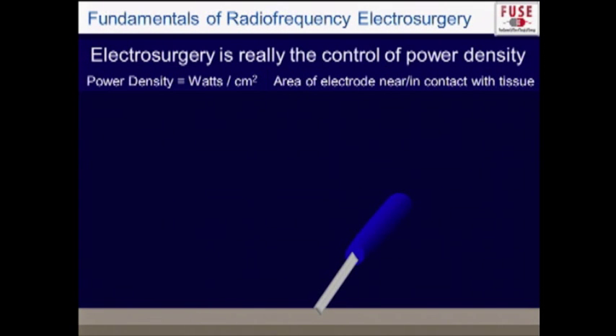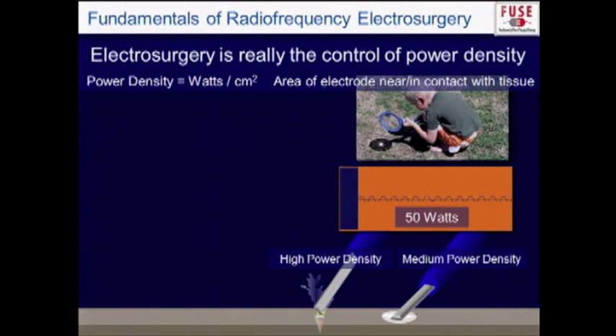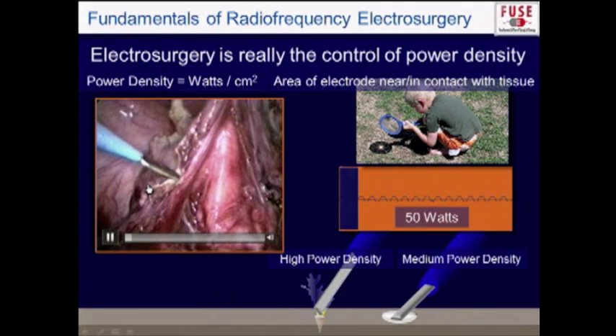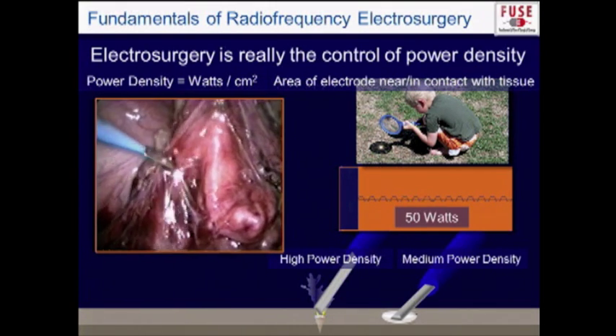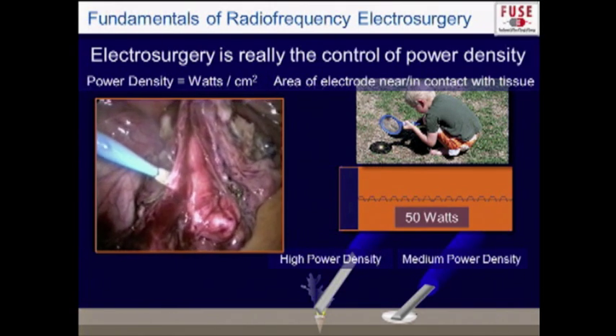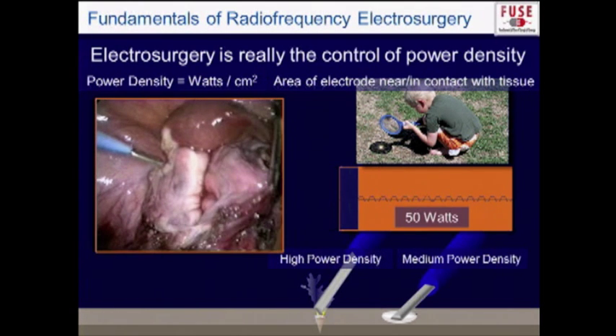Taking a blade electrode in two different orientations demonstrates this clearly. Edge-on to the tissue creates high current density; flat against the tissue creates medium current density. Using the same so-called cut, low-voltage output: the edge-on orientation produces vaporization — cells explode — while the flat orientation produces desiccation. This is demonstrated at 50 watts with cutting output — rotating the electrode from edge to flat instantly changes the tissue effect from vaporization to desiccation and back.